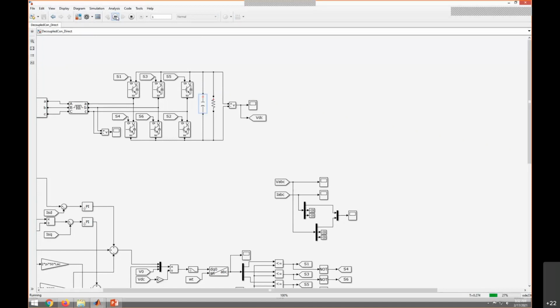Okay, sir. I will show you that. Sometimes we need to pre-charge this capacitor because the source currents are increased a lot, right? We usually have some fuse or some protection equipment. So when you try to start, we can experience that the fuse or that MCB will be triggered. So therefore what we have to do is to pre-charge the capacitors.